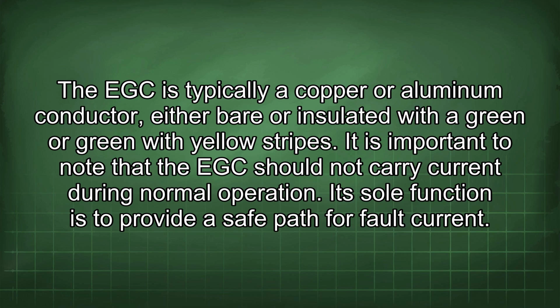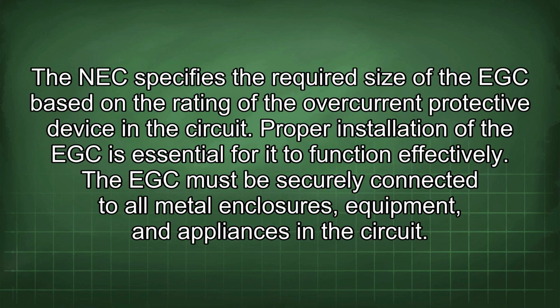The EGC is typically a copper or aluminum conductor, either bare or insulated with a green or green with yellow stripes. It is important to note that the EGC should not carry current during normal operation. Its sole function is to provide a safe path for fault current. The NEC specifies the required size of the EGC based on the rating of the overcurrent protective device in the circuit. Proper installation of the EGC is essential for it to function effectively.